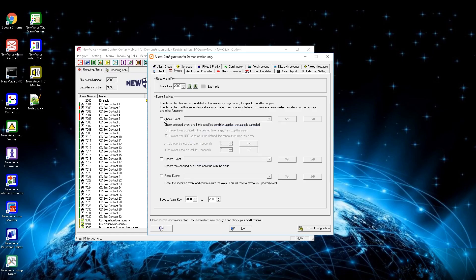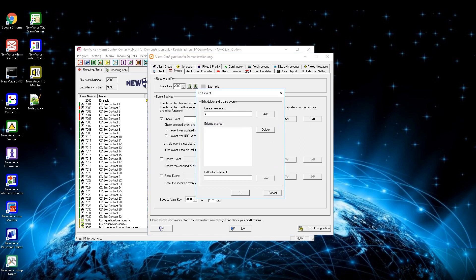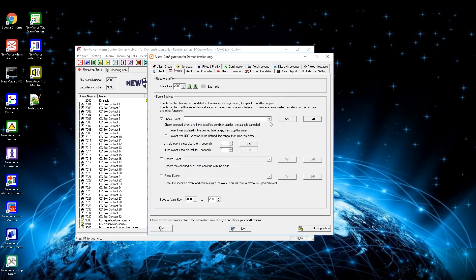With MobiCall you can also create events on alarm start and check specified events to avoid multiple alarming from an interface. Activate the box check event and press on edit at the right side. Here you can add, delete, or edit your events. After creating events, select one from the drop-down menu. Below you can define what should happen — it is possible to say if the event was updated or not updated in the defined time range then stop this alarm. Below can be set if the event is not too old or is too old. With the option update event you can update specified events, and the last setting resets a specific event and continues with the alarm.